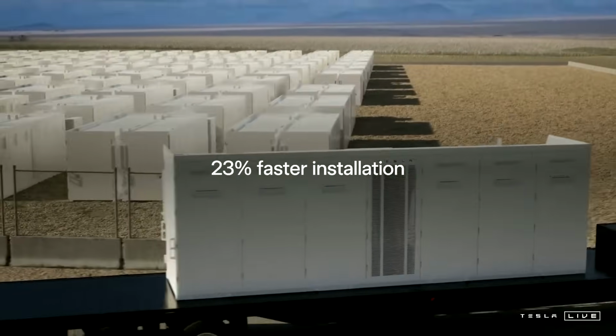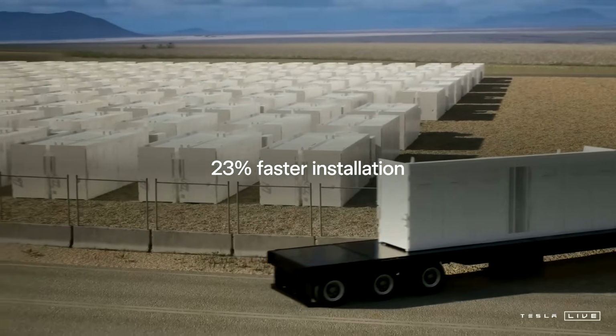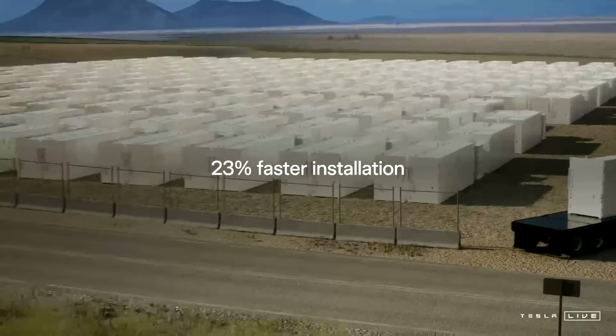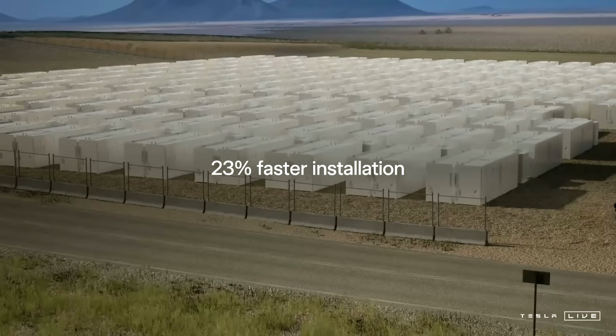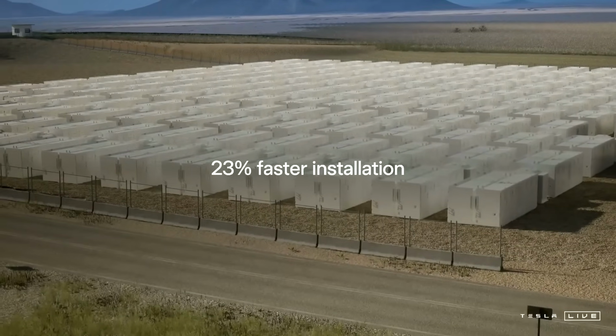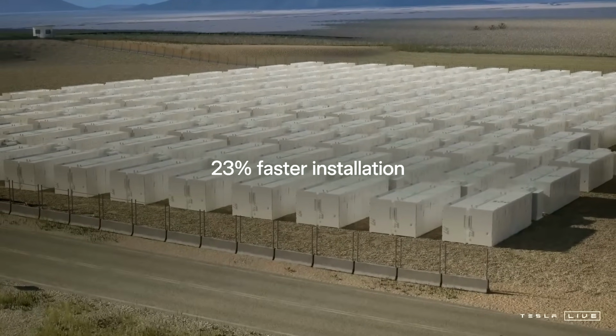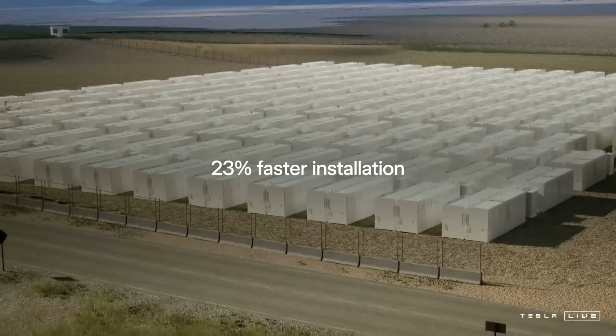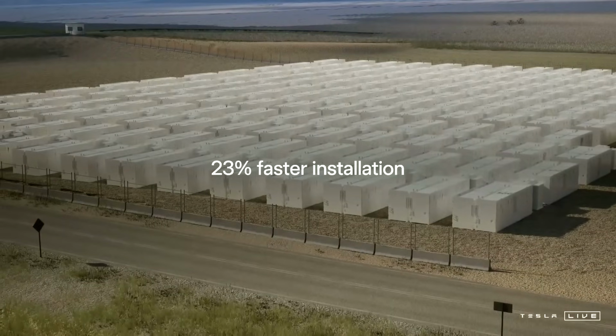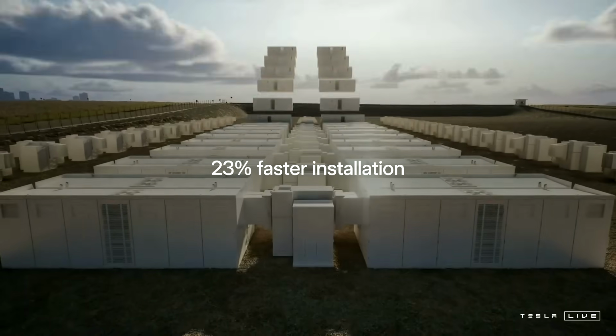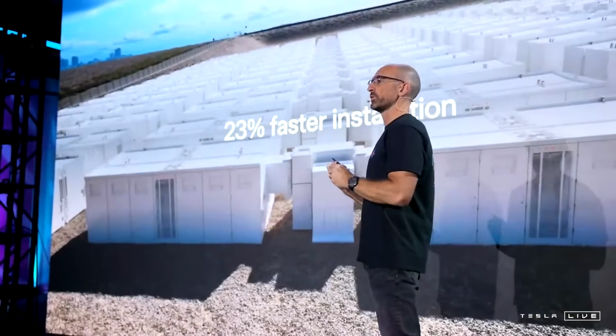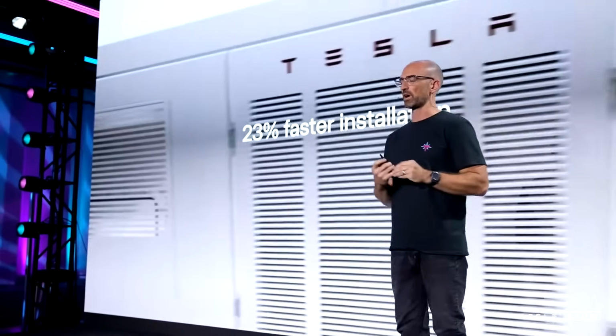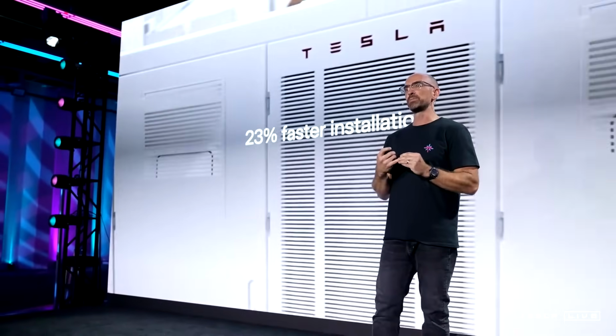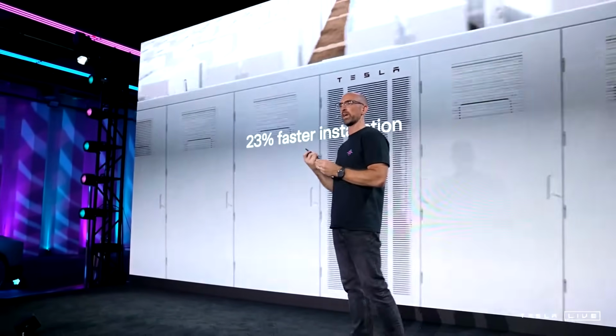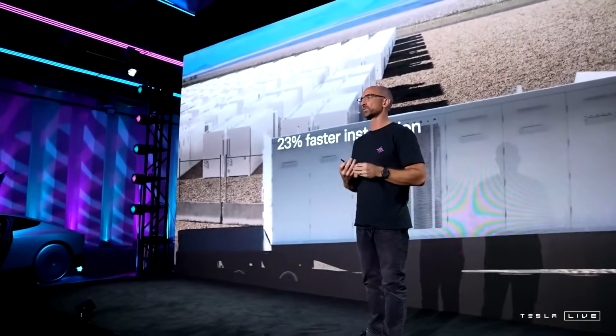We wanted to do what we did well with Megapack 2 XL, which was build a product in the factory that is factory tested, shipped to the field, ready to connect to the grid with zero on-site assembly. Megapack 3 can be easily transported using a 7-axle trailer with no on-site assembly, and with a higher energy rating we need fewer megapacks, reducing costs. We also went from up to 24 cable connections between the megapack and the transformer down to just 3 simple bus bar connections.